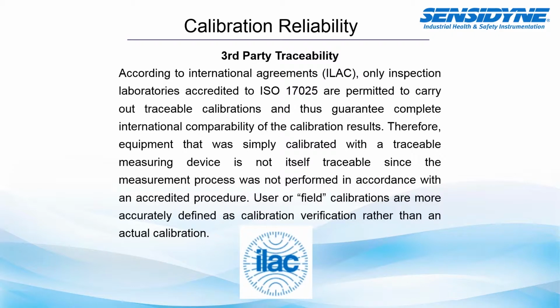According to the international agreements, ILAC, only inspected laboratories accredited to the ISO 17025 standard are permitted to carry out traceable calibrations and thus guarantee complete international comparability of calibration results. So you'll see at the bottom of this the ILAC certification, and again, you'll usually find this accompanied by the ISO 17025 certificate, as well as information like the A2LA certification.